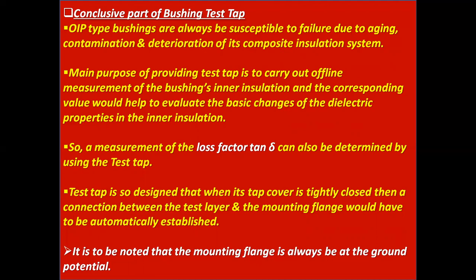The main purpose of providing a test tap is to carry out offline measurement of the bushing's inner insulation, and the corresponding value helps to evaluate the basic changes of the dielectric properties in the inner insulation with their service life. So, a measurement of the loss factor tan delta can also be determined by using the test tap.